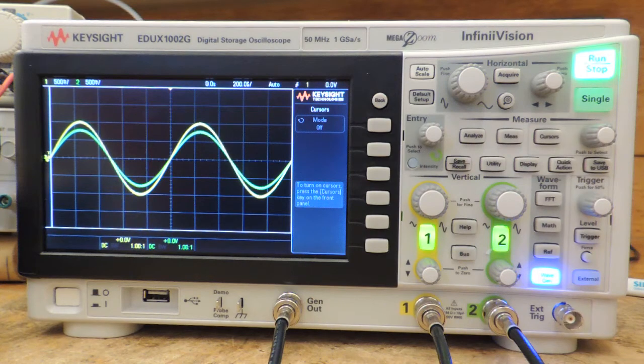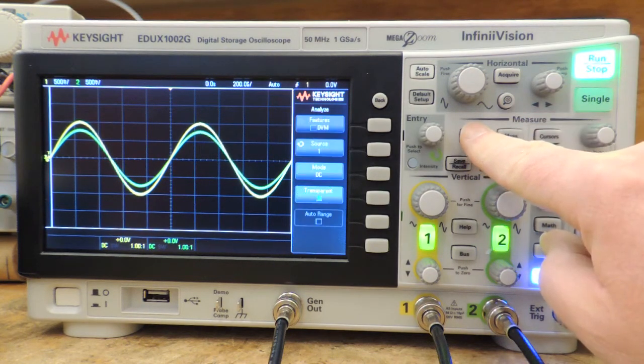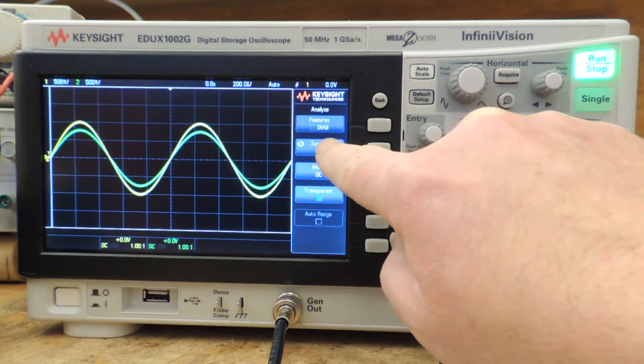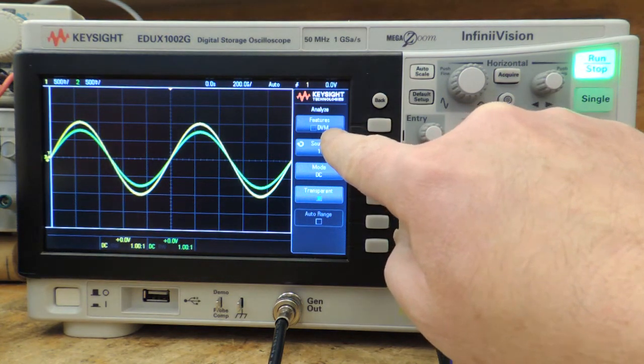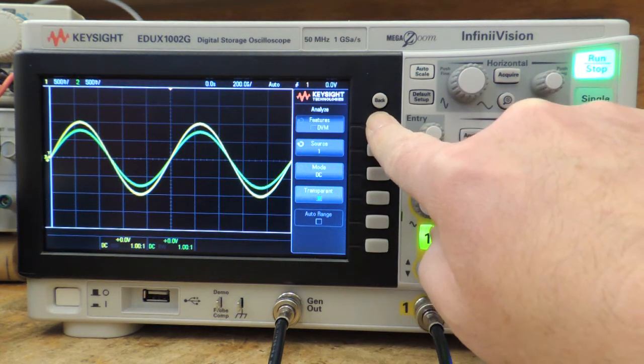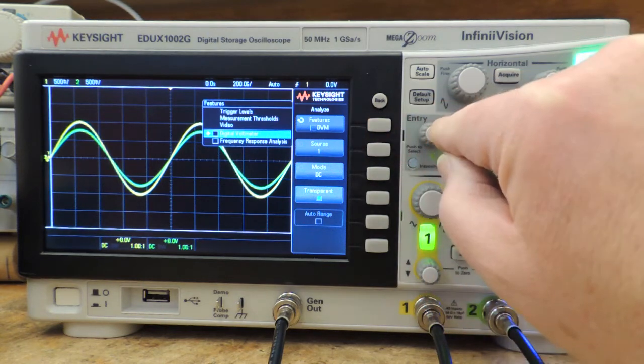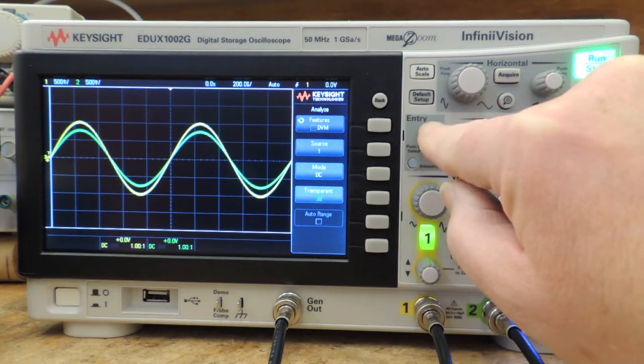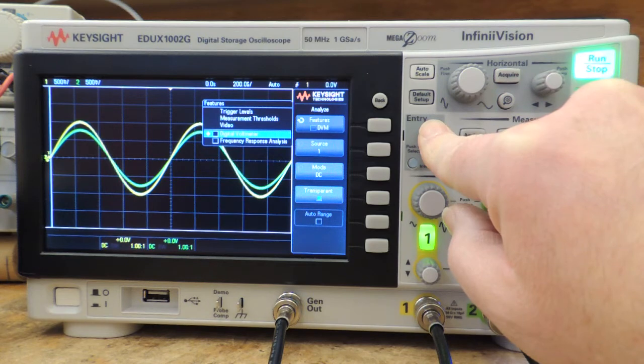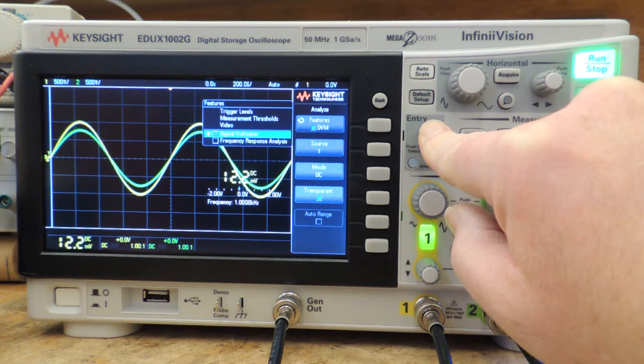So under procedure step 13, it says you can also use the Analyze button, and it features DVM. So if we press the analyze button, and the first item that comes up is features DVM, so press that button. Then the entry knob, press it in and select digital voltmeter.